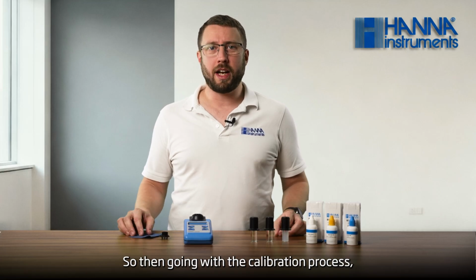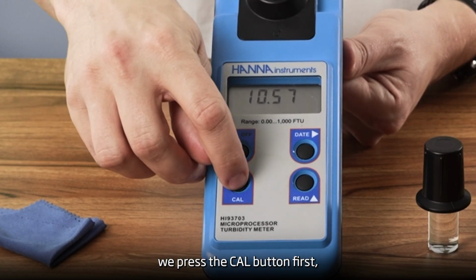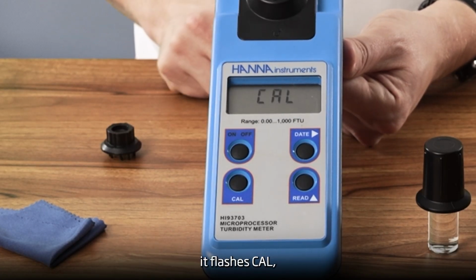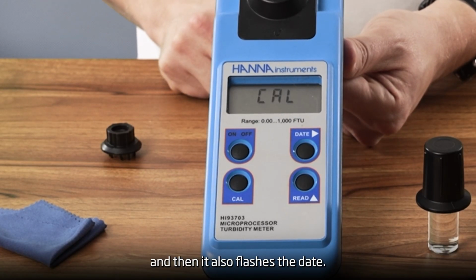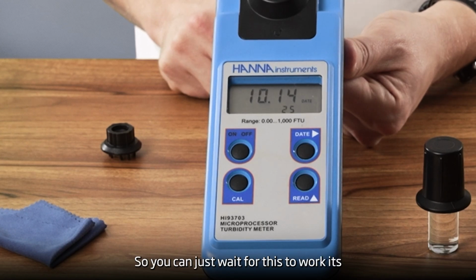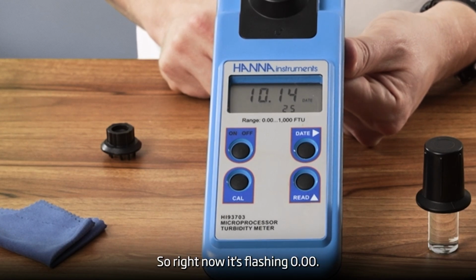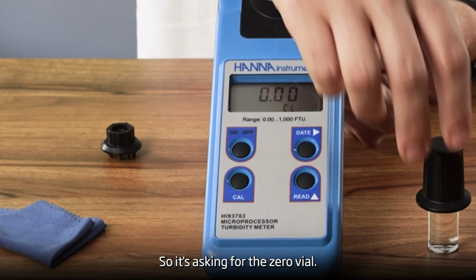So then, going with the calibration process, we press the cal button first, it flashes cal, and then it also flashes the date. So you can just wait for this to work its way through to the calibration phase. So right now it's flashing 0.00, so it's asking for the 0 vial.